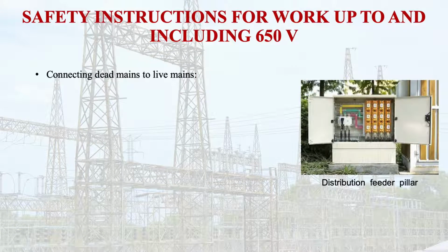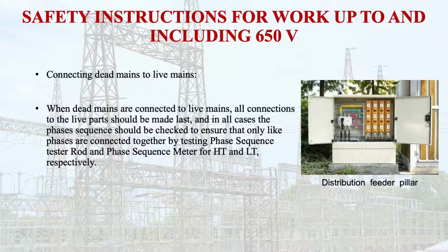Now, connecting dead mains to live mains. When dead mains are connected to live mains, connection to the live parts should be made last, and in all cases the phase sequence should be checked to ensure that only like phases are connected together, by testing with a phase sequence tester rod and phase sequence meter for HT and LT respectively. So for checking the phase sequence, we can use the phase sequence tester rod.